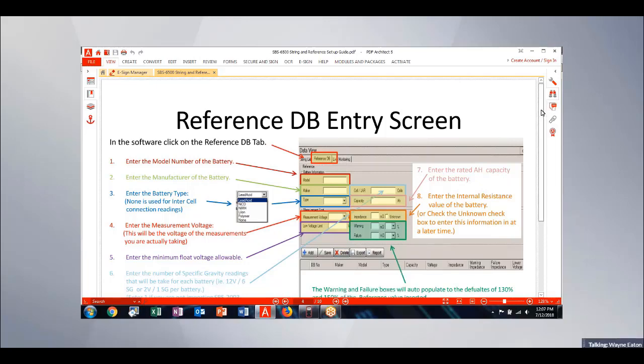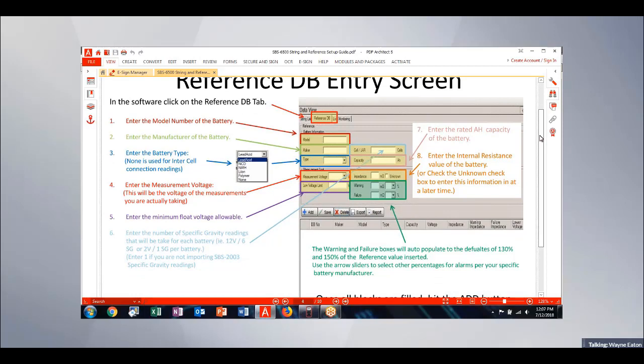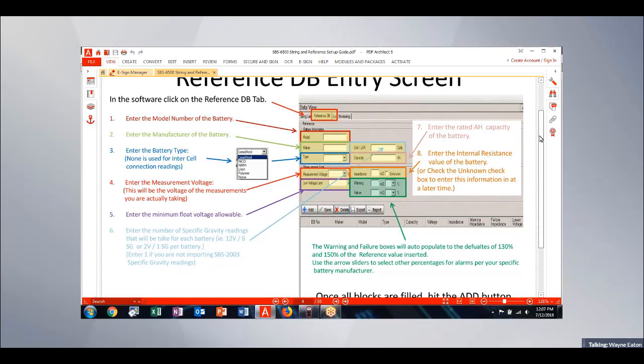So in the software, we've got basically 3 tabs that we work with. We've got a string list tab, and then we have a reference database tab, and finally we have a live monitoring tab. In order to set up a string or a measurement location, I have to have a reference database entry that I can tie that string to. So the first thing is to set up a reference database entry. Hit the reference database tab, and I'd enter the battery model, manufacturer, and the type of battery: lead acid, nickel cadmium, nickel metal hydride, lithium ion, some other polymer, or none.